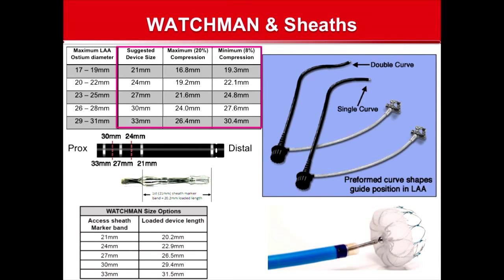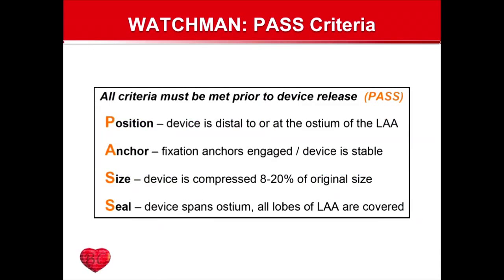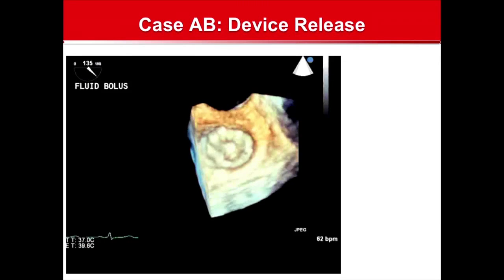And we certainly, based upon the instruction for use, want to have a compression of 8 to 20%, which was achieved here. So we look at these 4 pass criteria: position, anchor based upon a Tug Test, sizing, where the compression of the device is 8 to 20% of original device size, and then seal, meaning there's no significant device leak of more than 5 millimeters. And if all these criteria were achieved, then we would release the device.